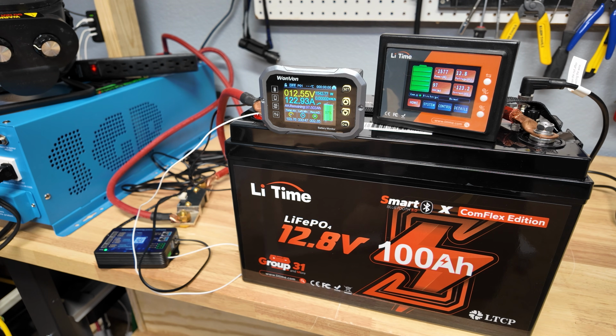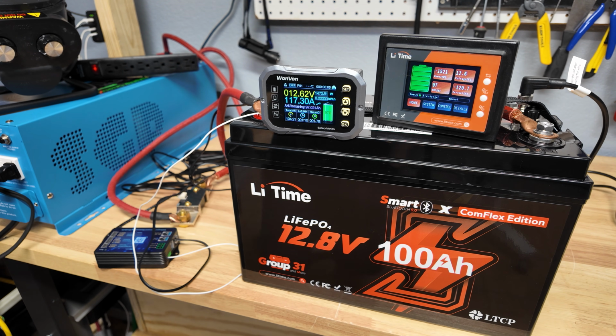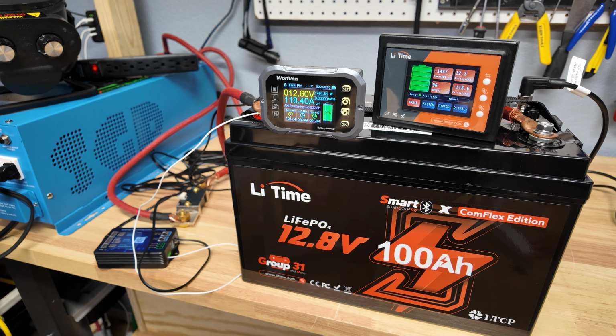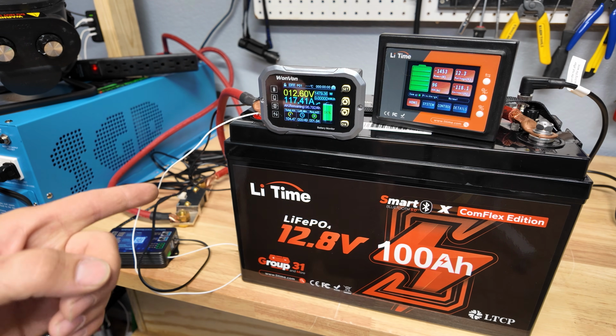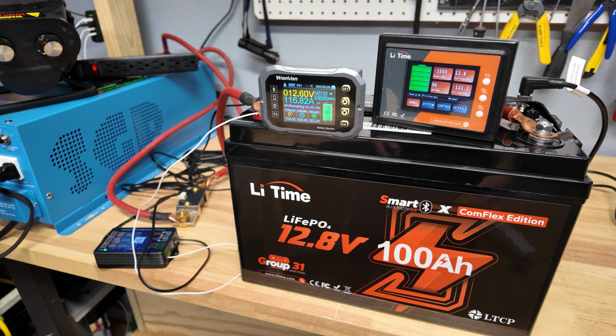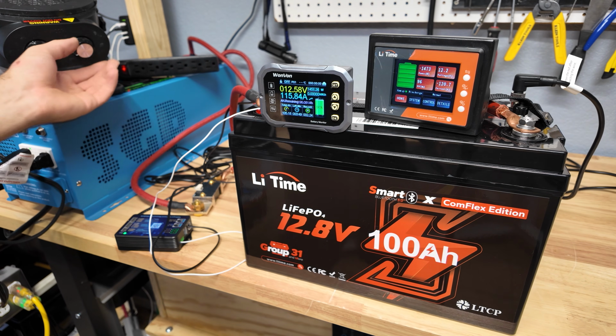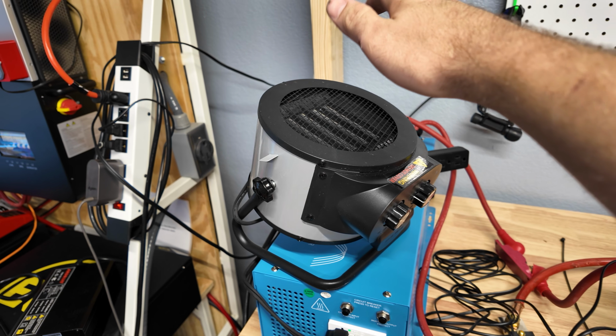Now I'm going to increase the load a little bit more. I added an additional battery charger that's going to put about another 400 to 500 watts worth of load. Space heater's on medium with the battery charger on, we're at 117 amps. Go ahead and crank the space heater up to high, 160 amps. A lot of heat coming out of that.